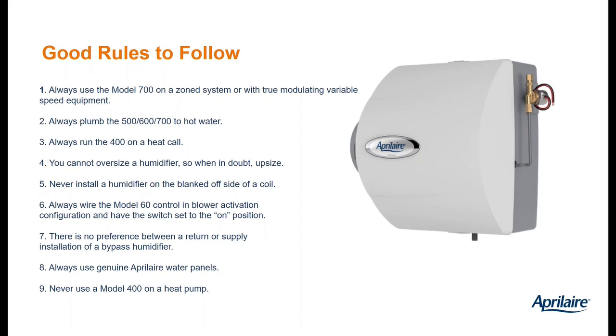The Model 60 always goes on the return. Always goes on the return, never up in the living space, never on the supply duct. And we strongly encourage you to supply the flow-through humidifiers with hot water and therefore put the Model 60 into blower activation on position. Bypass humidifiers work exactly the same, whether the bypass humidifier itself is on the supply and the bypass duct goes to the return, or the opposite is true: the bypass humidifier goes on the return and the duct goes over to the supply. No difference. Same airflow, same air temperature. Water, airflow, heat, you're going to get the same amount of evaporation.